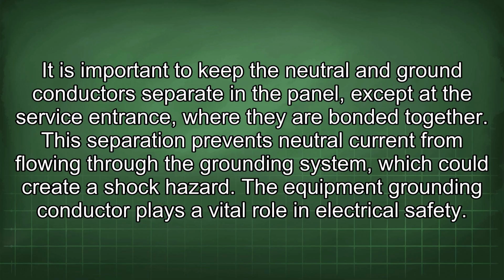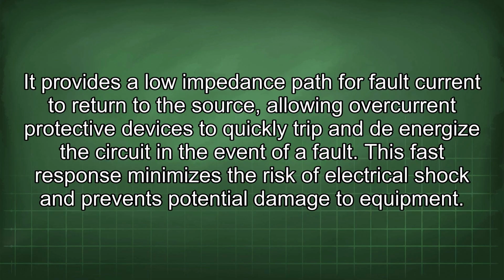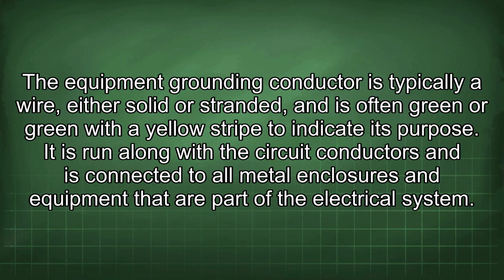hazard. The equipment grounding conductor plays a vital role in electrical safety. It provides a low impedance path for fault current to return to the source, allowing overcurrent protective devices to quickly trip and de-energize the circuit in the event of a fault. This fast response minimizes the risk of electrical shock and prevents potential damage to equipment. The equipment grounding conductor is typically a wire, either solid or stranded, and is often green or green with a yellow stripe to indicate its purpose.